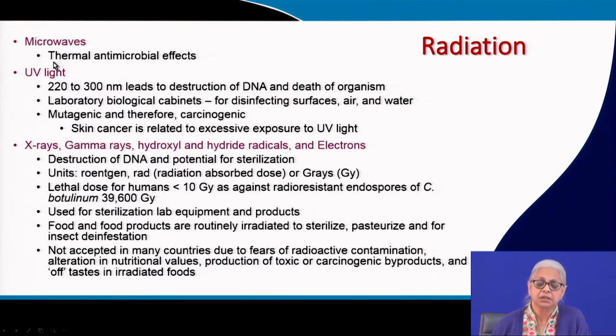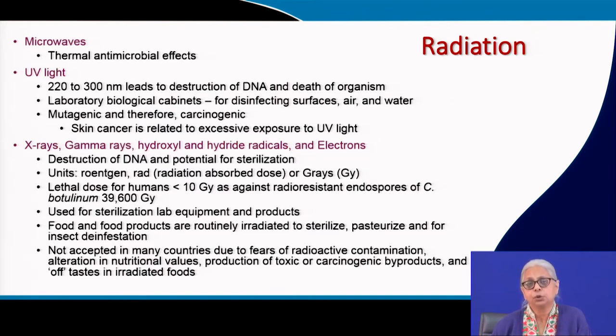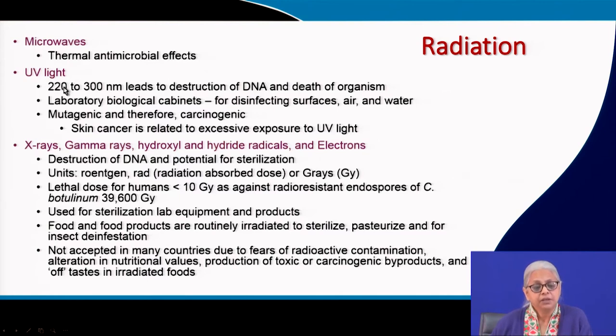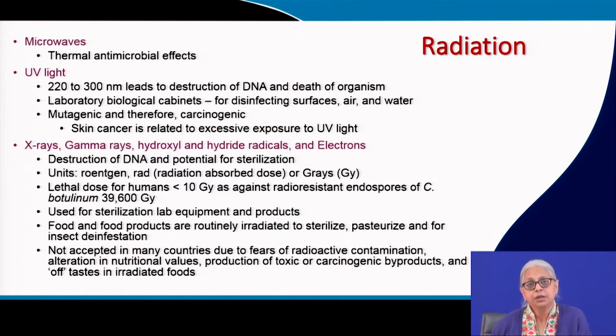UV light has become a standard part of what is called end of pipe treatment or home appliances that we use for water treatment. UV radiation has become a standard physical method for disinfecting drinking water. The wavelength used is 220 to 300 nanometers. It can destroy the DNA and cause death of the organisms, making it a fairly effective way for ensuring that there are no pathogens in the water.